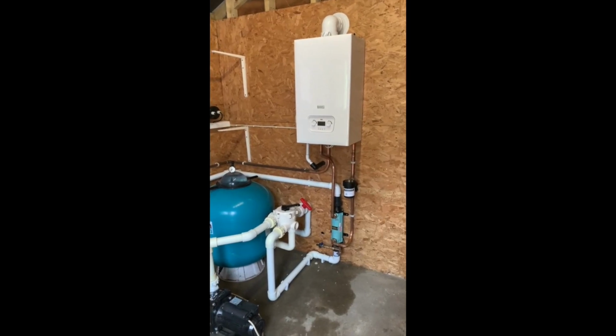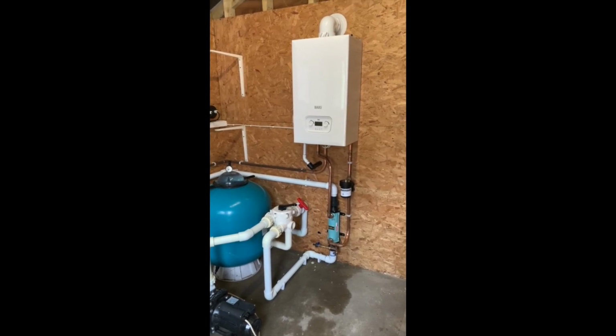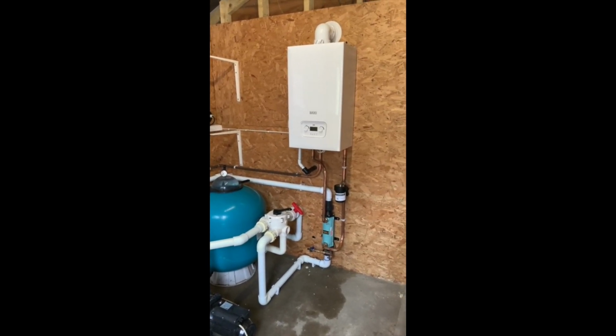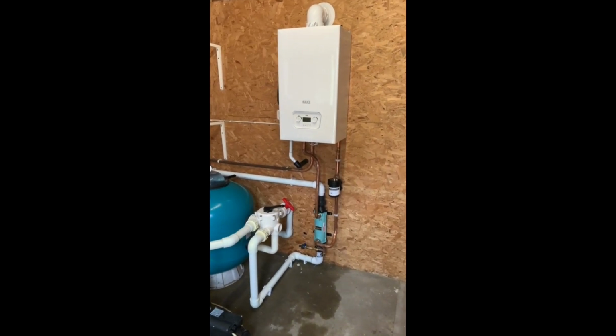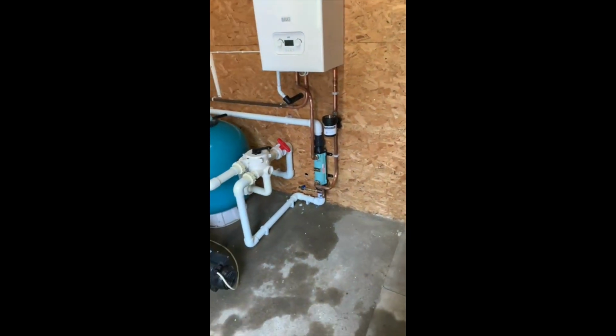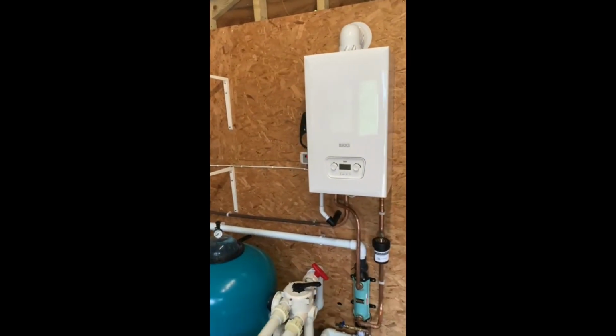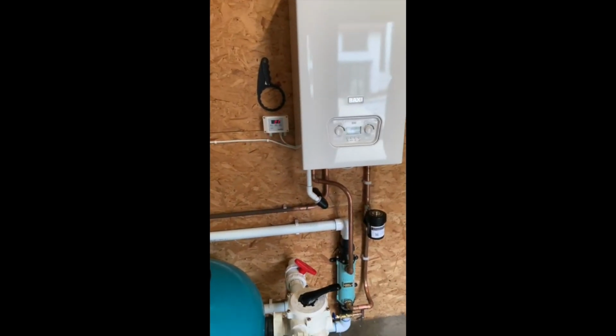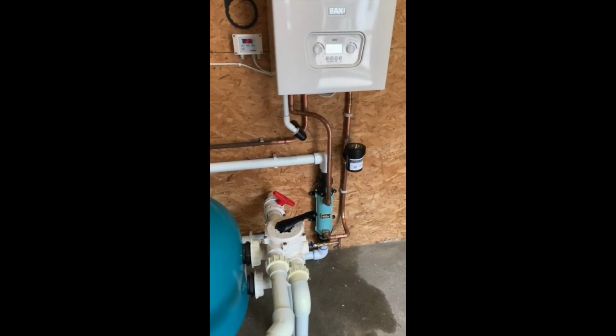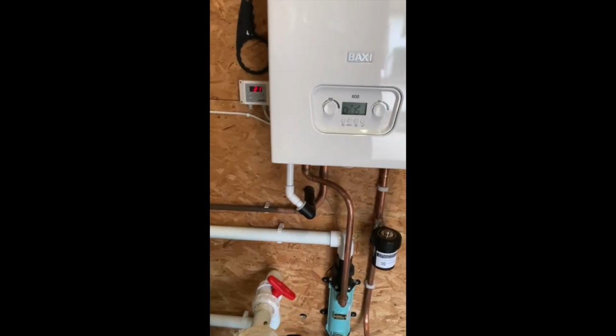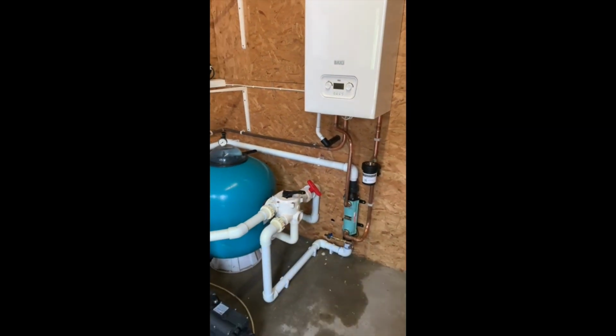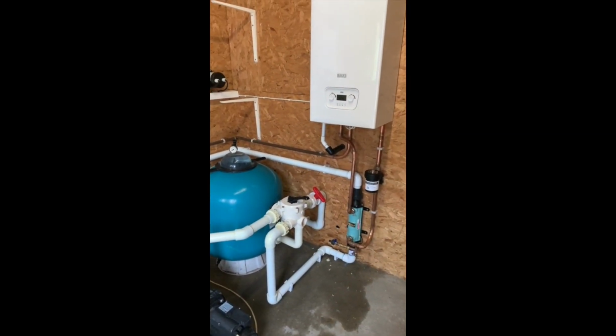Just going to take you through today's installation of a Baxi 30 kilowatt boiler conversion. So what we've taken out outside the property, there was an old Pentair. You can see the witness mark. There was this plate on here that we had pipe work going outside the property to an external boiler. We've mounted our Baxi 800 firmly, and we've placed the Bowman Heat Exchanger below that, and we've also got a condensate going out into a condensate limestone chipping trap outside. So very, very simple operation.